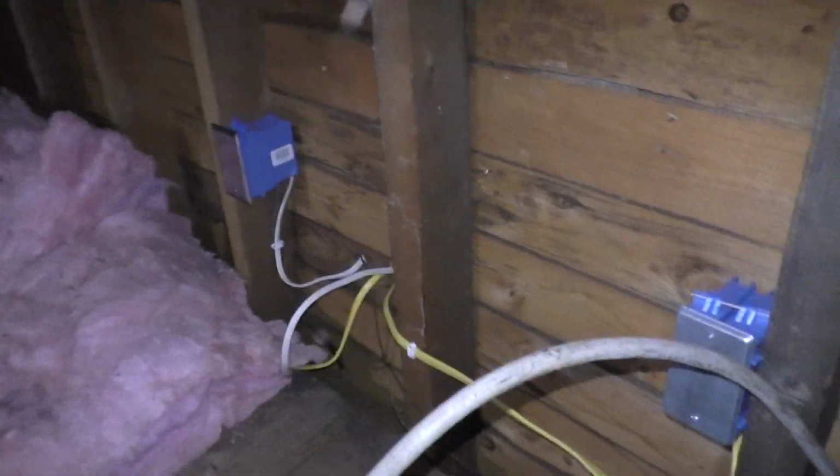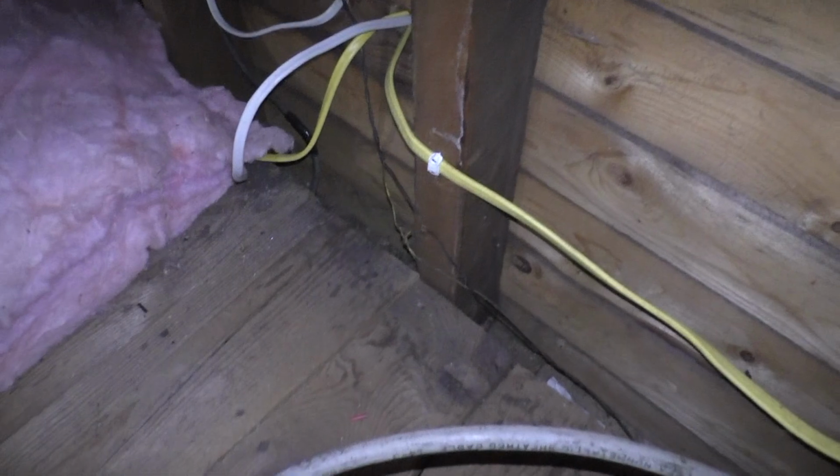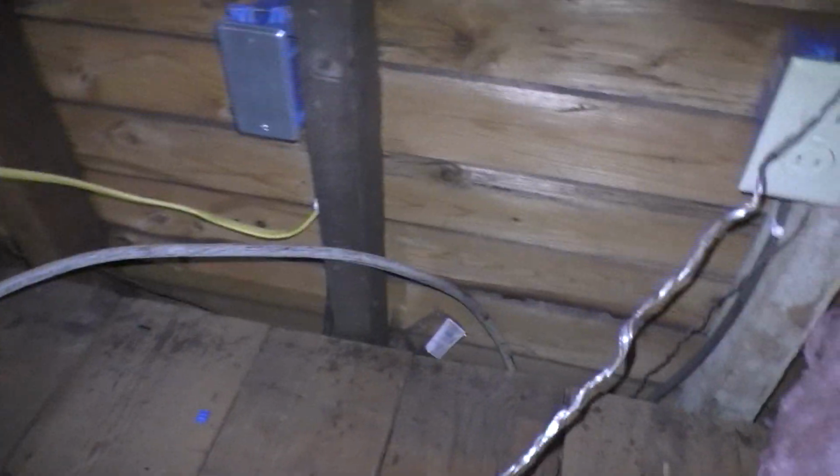So we're gonna cut it. We're gonna put another junction. This is gonna be junction boxes, and that's fine as long as they're exposed. They're legal. And as long as they're covered, they're legal. I looked into it. But I don't want to put another junction box if I can avoid it. What I want to do is I'm going to pull this back, and we're going to run it back down this chaseway here. Or this one. Or that one. Then we're going to pull a new wire.